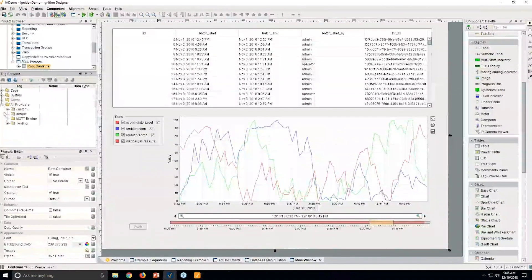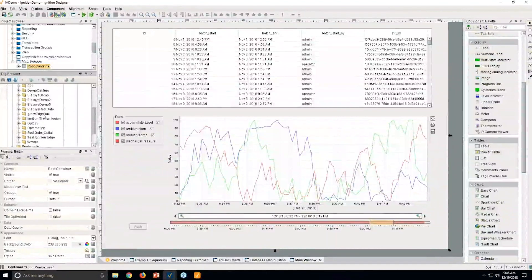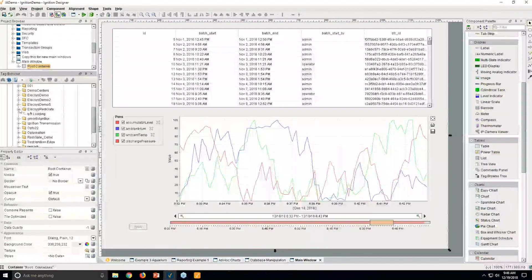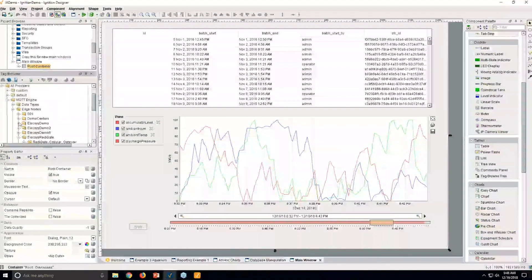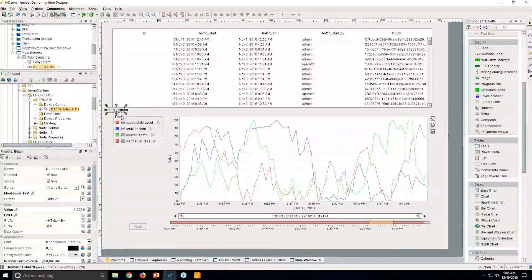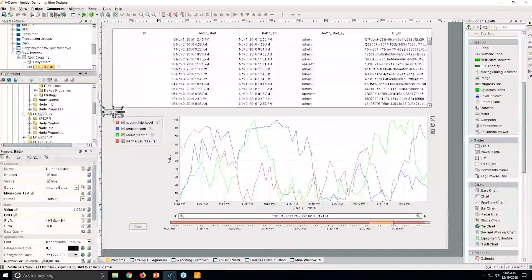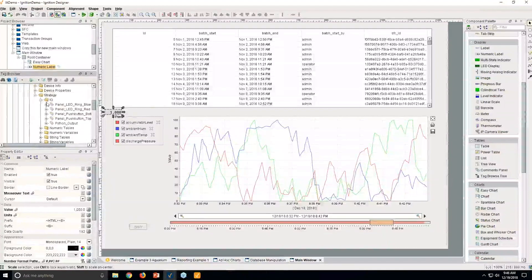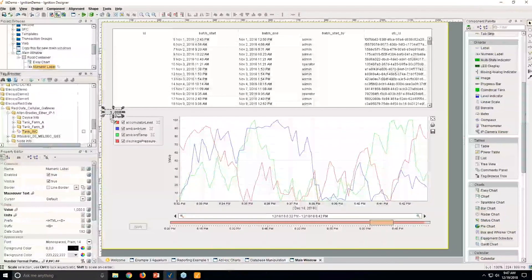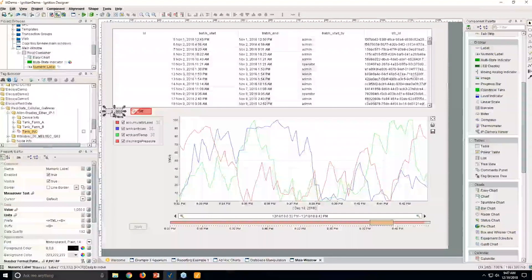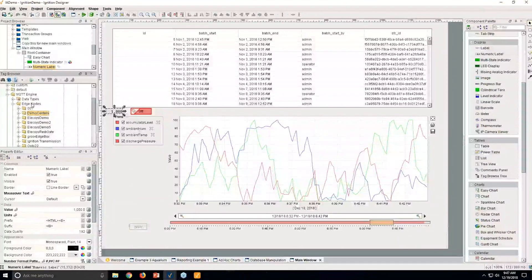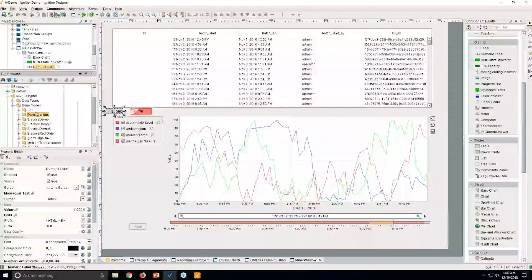Looking at all providers, I go to MQTT Engine and expand it out. There's a whole variety of edge nodes available from the brokers I'm connected to. If you're using an IIoT type of infrastructure, this information comes through right away. This shows connected Allen-Bradleys, for example, and some demo centers with EPICs sending information regularly. I can drag these out to the screen and see the values changing. Quality is shown as well — if tags are disconnected they'll come through as red, like this tank right here; if connected live, you see real values. It's a super lightweight protocol, allowing you to connect to really large infrastructures with millions of tags, easily accessible without extra configuration in Ignition.